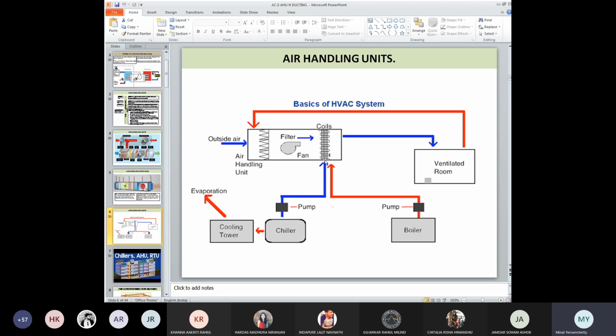Somebody asked me last year, I guess, that I will need a cooling coil here also. Why can't I have a single coil working as cooling as well as heating? A very valid question. You can do that. यहाँ पे एक valve लगा दो, जिसको आप सेंसर लगा दो. जैसे जैसे वो हीट सेंस करेगा, the valve will change and will only allow that component of water to go in. So then I'm controlling.